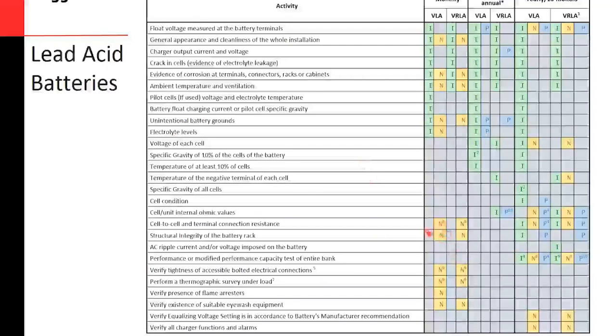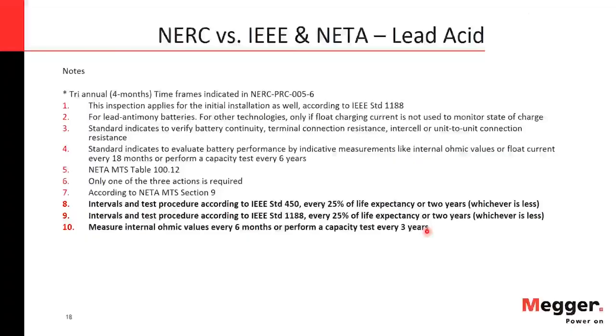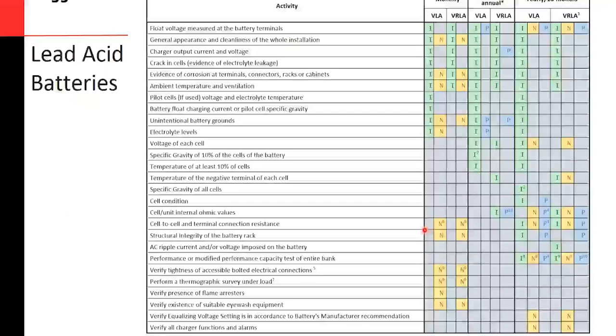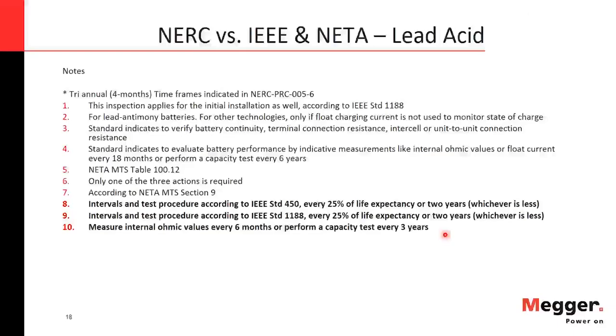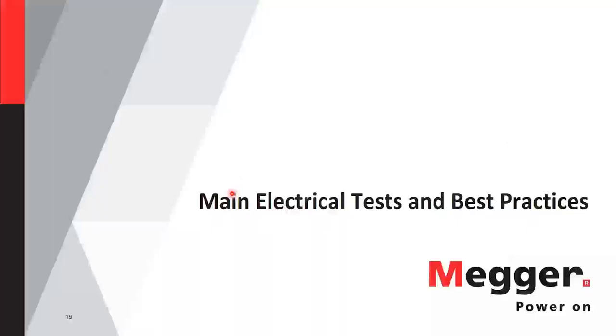And of course there are some notes. You can see some numbers here associated with one standard. So we have a table with footnotes, and for example, for the previous one, cell-to-cell terminal connection resistance, it has number 6. That means that only one of the 3 actions is required. So in NERC and in NETA, for example, to verify the continuity of the battery, they ask only for one action. NERC asks for a cell or a strap resistance measurement, the battery continuity, and also one additional action there. So this will help you a lot, and as I said, we can provide these tables if you contact us.